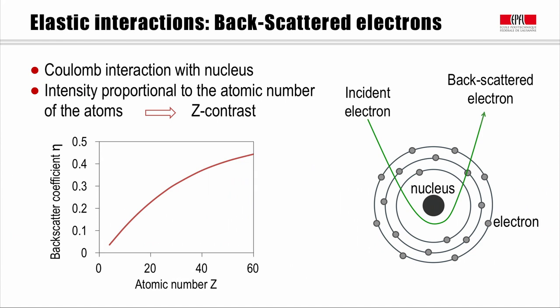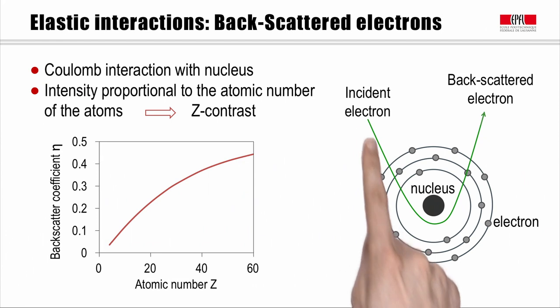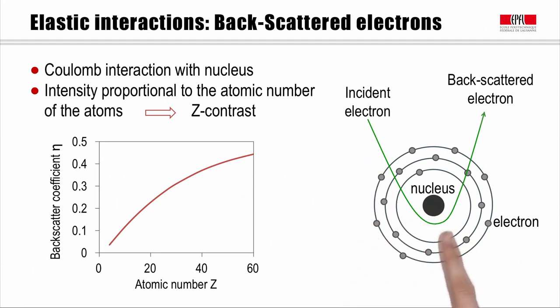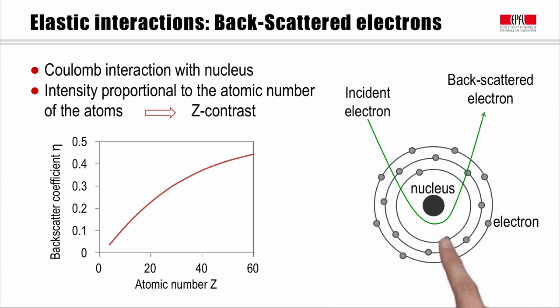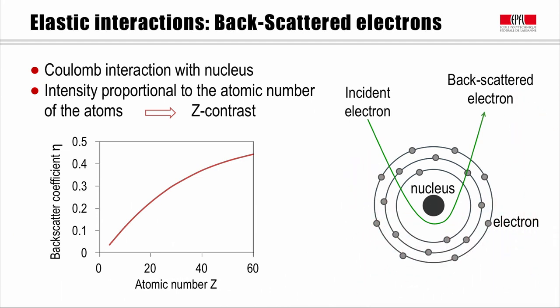Another kind of interaction occurs when an incident electron feels the Coulomb interaction with the nucleus of an atom of the sample. This incident electron is deviated because of this Coulomb interaction. If this deviation leads to high-angle diffusion, the electron can leave the surface and be collected by the backscattered electron detector. This electron scattered back is called a backscattered electron, or BSE. This interaction is almost elastic — there is almost no energy transfer — which means the energy of backscattered electrons is very similar to that of the incident beam.